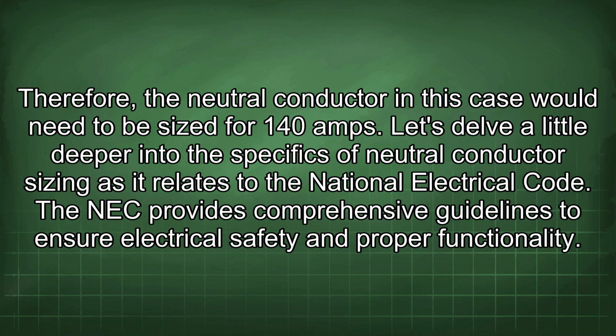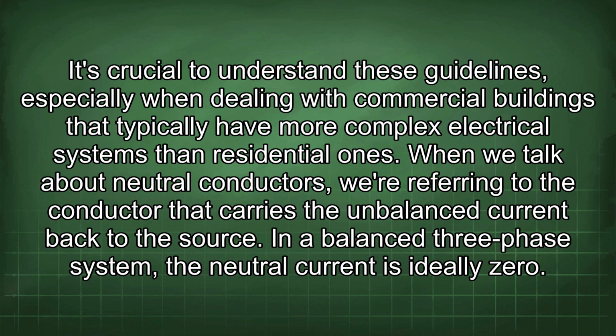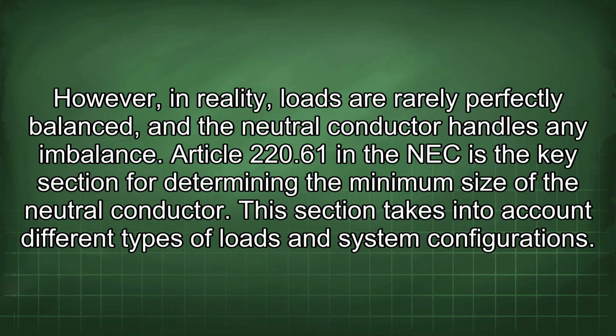Let's delve a little deeper into the specifics of neutral conductor sizing as it relates to the National Electrical Code. The NEC provides comprehensive guidelines to ensure electrical safety and proper functionality. It's crucial to understand these guidelines, especially when dealing with commercial buildings that typically have more complex electrical systems than residential ones. When we talk about neutral conductors, we're referring to the conductor that carries the unbalanced current back to the source. In a balanced three-phase system, the neutral current is ideally zero. However, in reality, loads are rarely perfectly balanced, and the neutral conductor handles any imbalance.